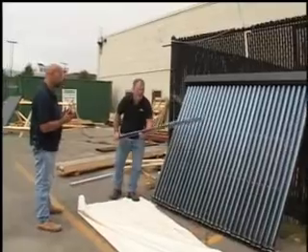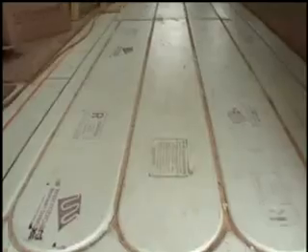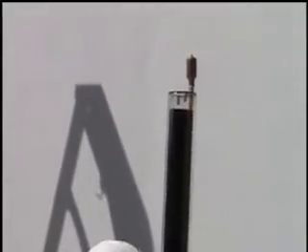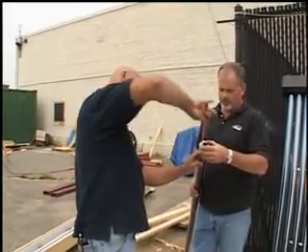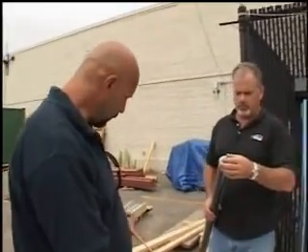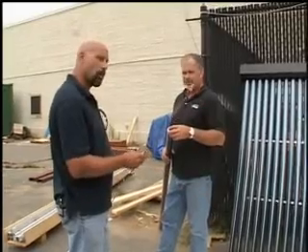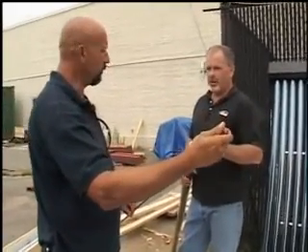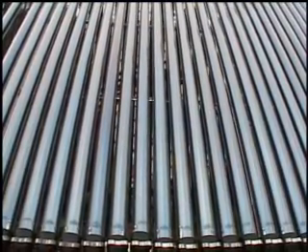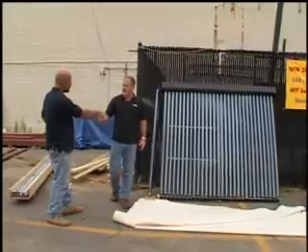This is definitely the most up-and-coming technology. We're mounting two of these systems on our south side, and they're going to provide all the hot water and radiant heat we need. Basically, this is a thermos bottle on the outside — it's got a vacuum between it and a metal coating on the inside that captures the heat. This tube is a heat transfer copper tube; that's where your actual energy comes out. Inside, there's a drop of water placed in a vacuum, which allows it to boil at a very low temperature — about 85 degrees. That water boils, comes up to the top of the condenser, the water flowing around transfers the energy, and then the drop falls back to the bottom and the process starts all over again. Tom, you're starting to educate me on solar homes. Thanks for the tour — looking forward to seeing this thing being done.